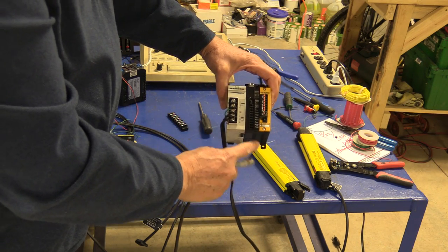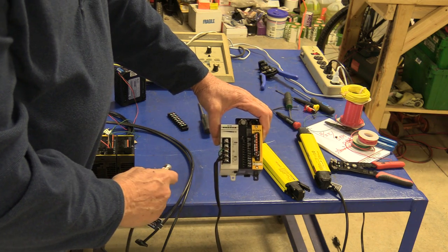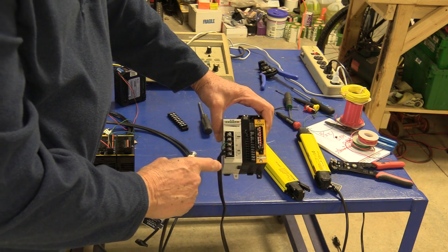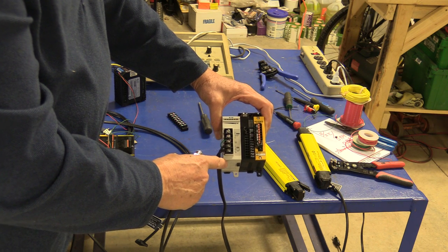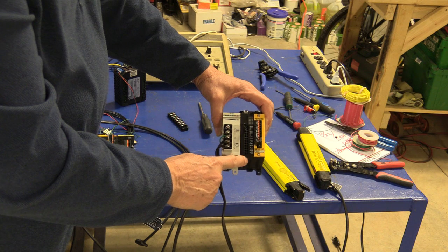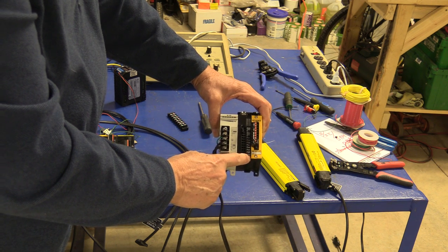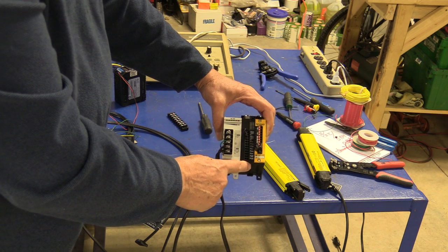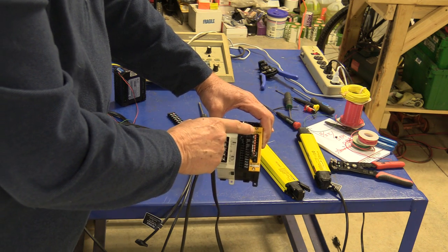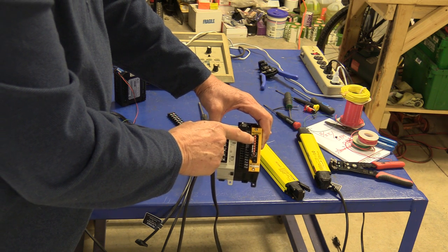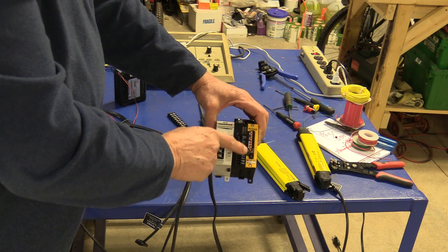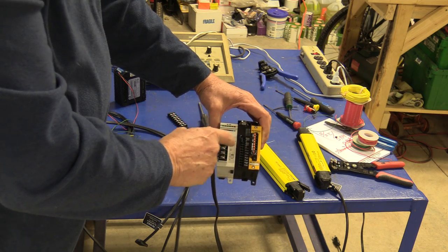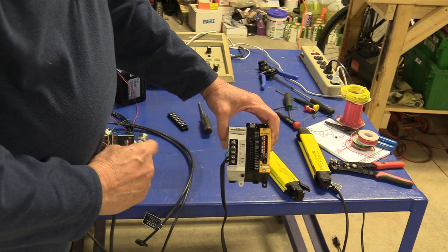The receiver and the transmitter have cabling that matches to this safety relay, which can interface and interpose with your other equipment. This is a power supply that Keyence sells at a reasonable price. Otherwise, you have to provide 24 volts. It's simply a safety relay with relay one and relay two, and some separate outputs you can get via the software. The software is free, which is the best kind.